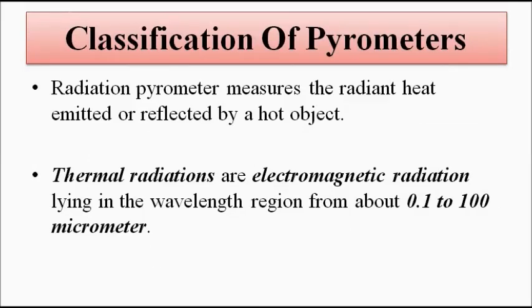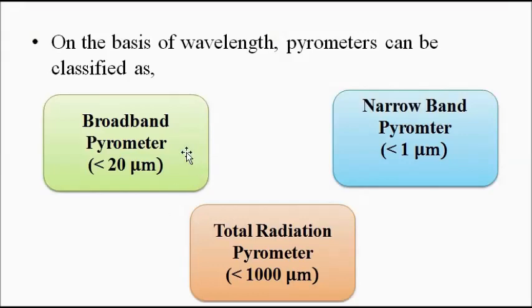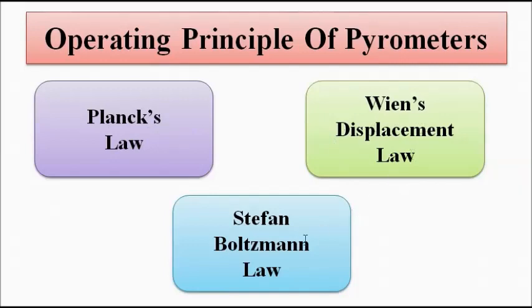There are different ways in which pyrometers can be classified. Since thermal radiations lie in the wavelength region from 0.1 to 100 micrometers, we can convert this wavelength range into different zones according to which pyrometers can be classified. For example, broadband pyrometers are used to measure radiations with wavelength less than 20 micrometers; narrow band pyrometers are used for measurement of radiations less than 1 micrometer; and total radiation pyrometers are used for measurement of thermal radiations less than 1000 micrometers. All measurements are related to the three laws: Planck's law, Wien's displacement law, and Stefan-Boltzmann's law.